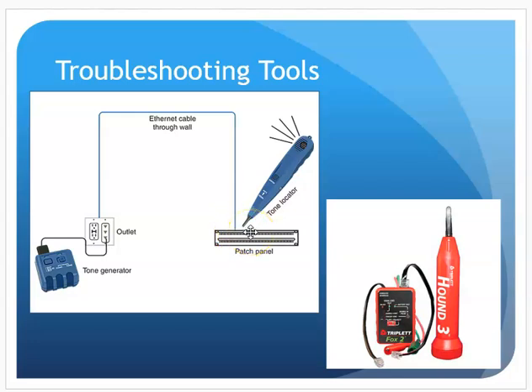When I get to the cable that has the signal on it, you'll literally hear it—usually a beep, beep, beep kind of tone. The speaker's on the back, and you'll hear that signal, which lets you know that's the cable. I might then notice it's labeled wrong, or now I know where it is. It's a super handy troubleshooting tool to find a cable or cable run—one of those tools you might only need for a few minutes, but it's priceless because it helps you find that cable very quickly.